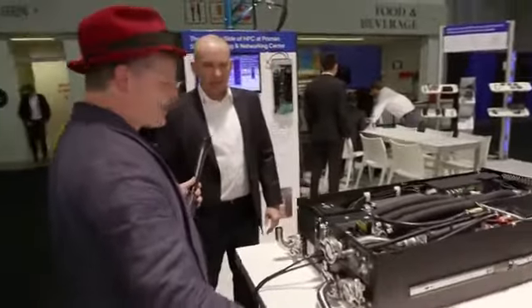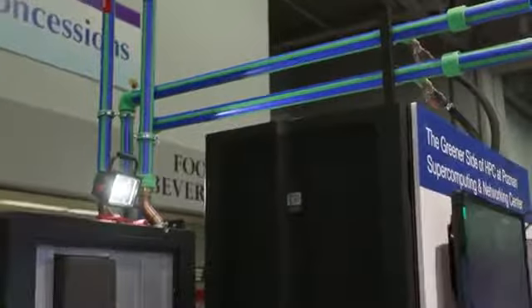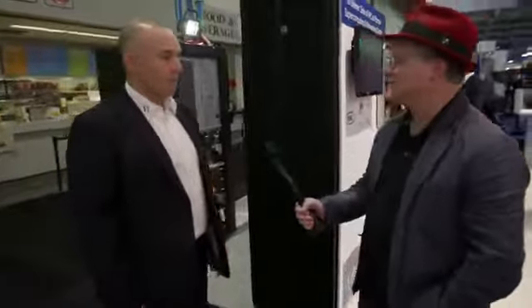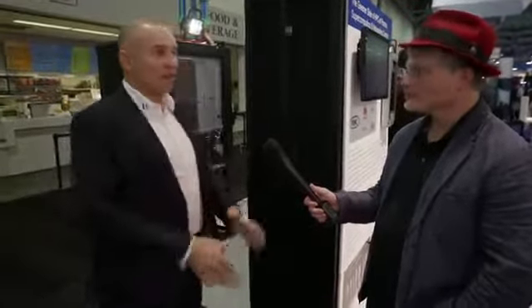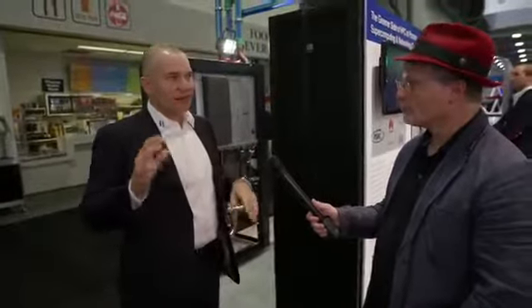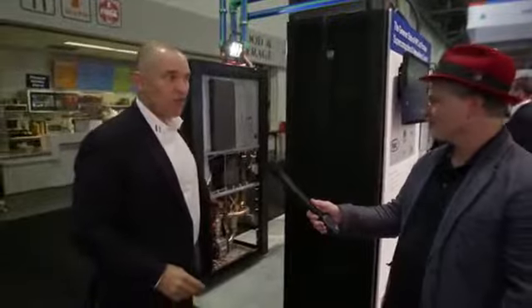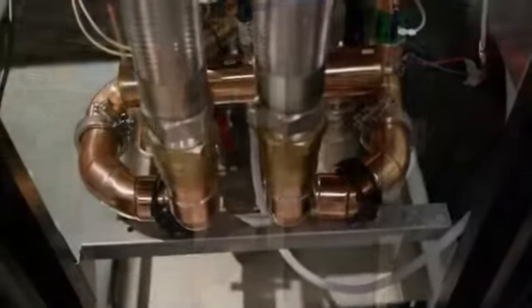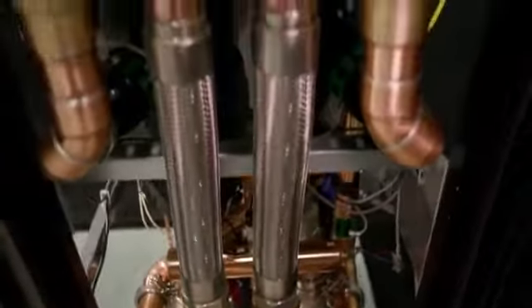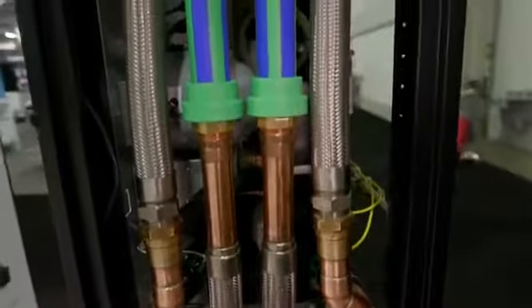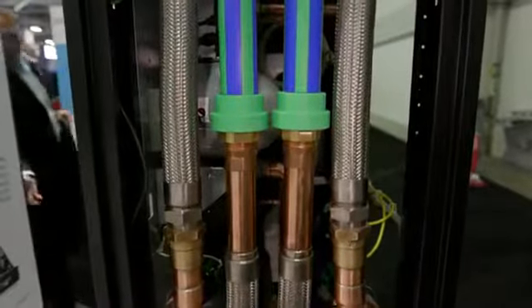It's a fantastic unit, and we're starting to ship these out to customers now, so we're excited about that. So Jeff, we're moving up the scale here now with some big capacity. That's right. Everything that we've talked about so far is kind of scalable rack units. What we've got here is actually a row-based CDU. So instead of putting a CDU inside every rack, this much larger form factor CDU can supply all the secondary coolant flow to 12, 14, sometimes 18 racks at a time.